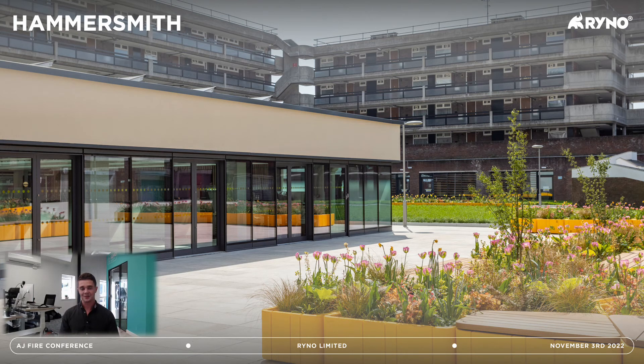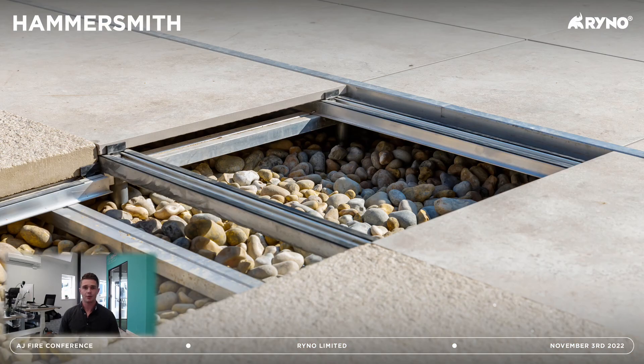With the apartments around the edge of the 6,000 square metre podium, we worked with a TerraSmart rail system. Instead of working with plastic pedestals, we went with a fully non-combustible system - the insulation was non-combustible and there was also the addition of a layer of 50mm ballast over the top to additionally enhance that fire penetration resistance, achieving more than just B Roof T4 and working to a non-combustible standard achieving a minimum of A2 S1D0 fire classification. You can see here the overall build-up - the rails, the aluminium joists, the mild steel pedestals supporting those porcelain tiles, and that 50mm ballast over the top.